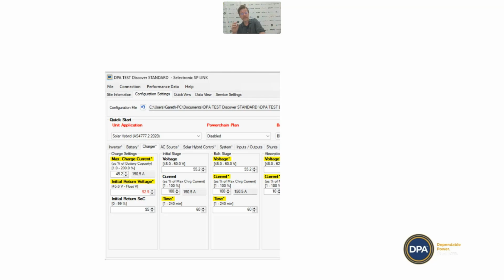Even though the maximum charge current on the specification sheet is 200 amps, it depends on how you measure it. The Selectronic inverters have massive capacitors and massive transformers, and compared to something like a transformerless inverter like the Deye, they have a lot of DC ripple just because of the topology. So there's peak current and there's RMS, and it depends on which one you're measuring when you say 200 amps is your maximum.